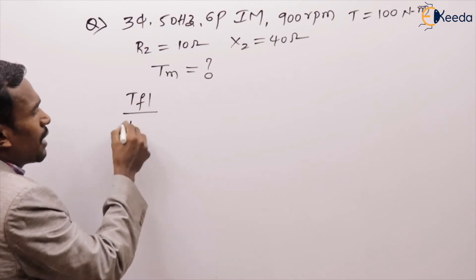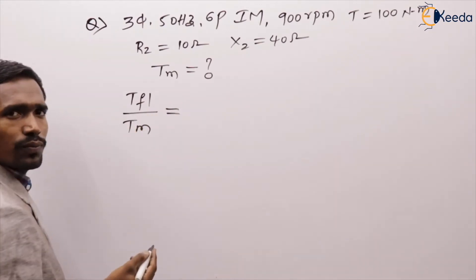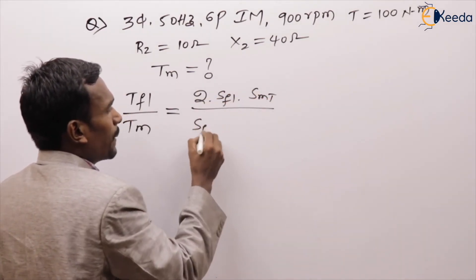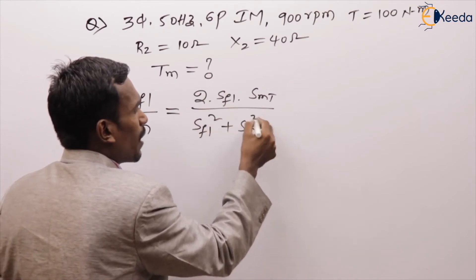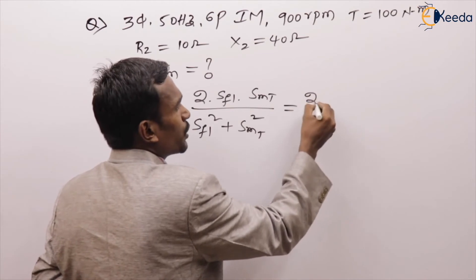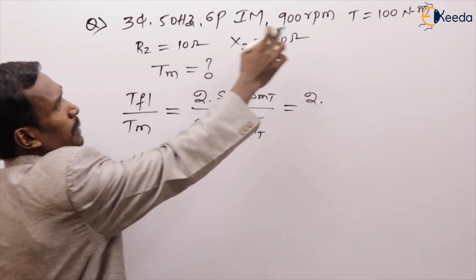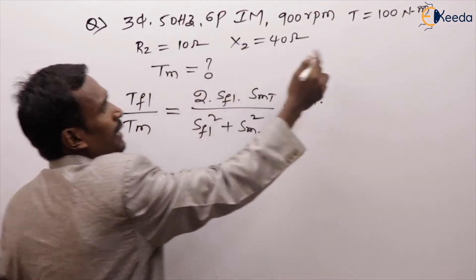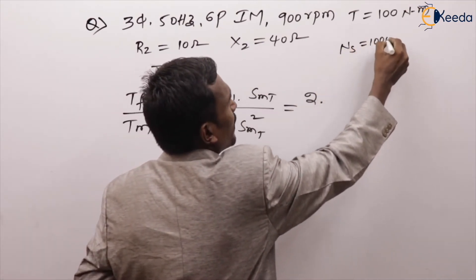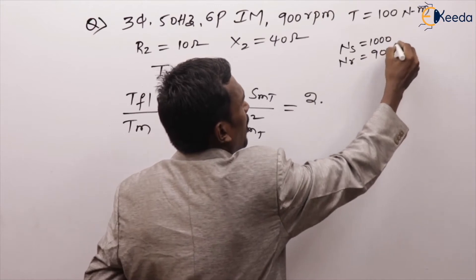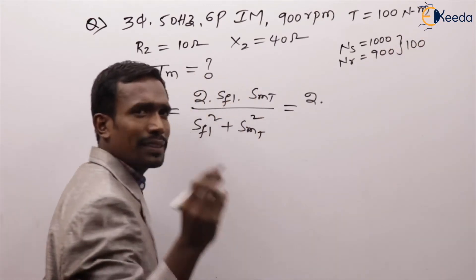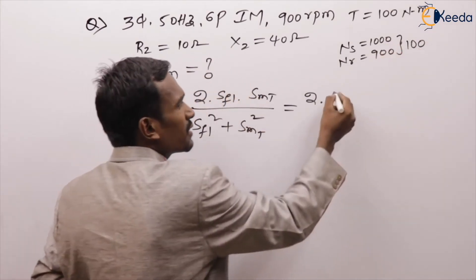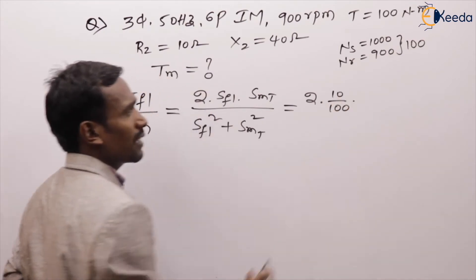The formula: full load torque to maximum torque = 2 × S_FL × S_MT / (S_FL² + S_MT²). The synchronous speed is 1000 RPM, rotor speed is 900 RPM, so slip = 100 RPM, which is 10% of 1000 — S_FL = 0.1.